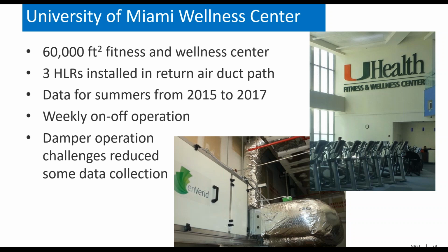But anyway, when we went to this building, they had a lot of challenges with their ventilation because it was neglected. Especially in Miami's hot, humid climate, they tend to close down their outside air dampers, often in the middle of the summer, to control the humidity, because they're often unable to meet the space conditioning requirements when it's hot and humid outside and they have a lot of outside air. So they'll close down those outside air dampers, or they'll get rusted in place. You can't operate them. So this building, when we first got there, was under pressurized, and it was sucking air in from the adjacent building. They also had a small pool, which is a separate space, but they were sucking air from there, which obviously is not a good condition.